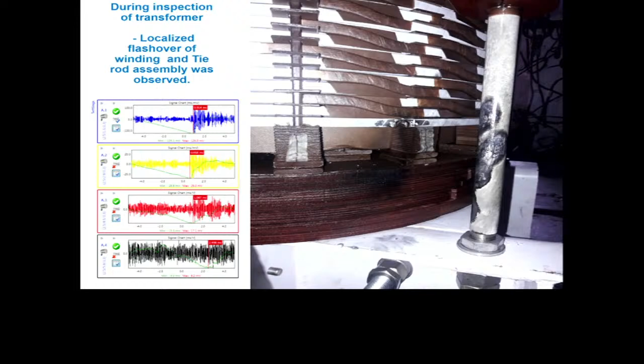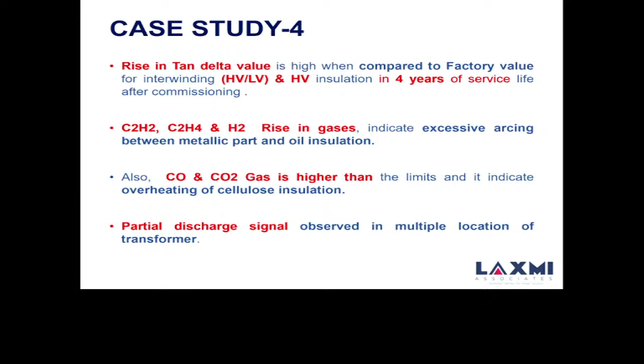This is another case where after 4 years we found acetylene in the DGA signal, but it was a kind of error where the tie rod had some nut bolts in between, giving continuous arcing between the active part and the tie rod. So that was removed after 4 years, and if it had stayed, it could have given a phase to earth fault after some time, but it was timely captured.